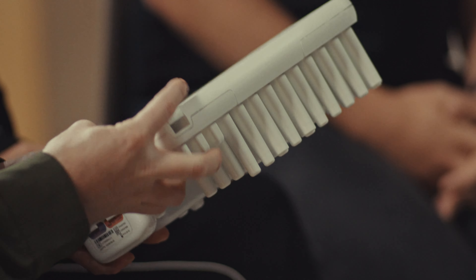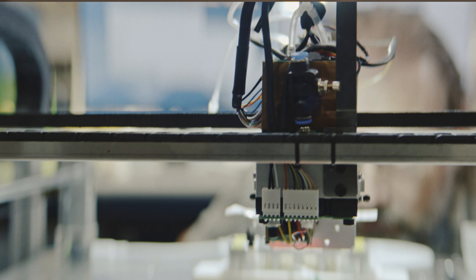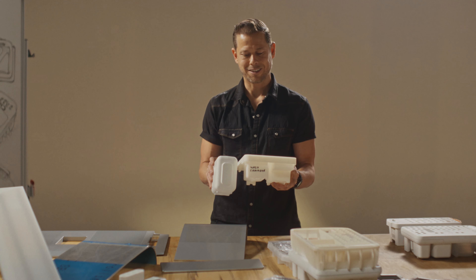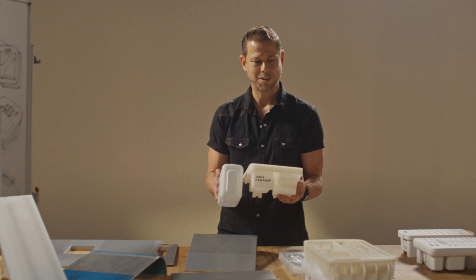From the very start of the program, we set a requirement that all consumables be disassembleable with no tools. We took it upon ourselves to make absolutely every component disassembleable by hand — no tools needed. They don't have to go find a screwdriver or a wrench; everything just pops out with minimal effort. The consumables team was tasked with the same challenge as the rest of the platform team: fitting everything into the same package size. We had to ask a lot of people to take on extra risk to give the user everything all at once, and getting that packaging to play well with the mechanisms and interactions of the instrument was a shared challenge that both teams were able to succeed on.